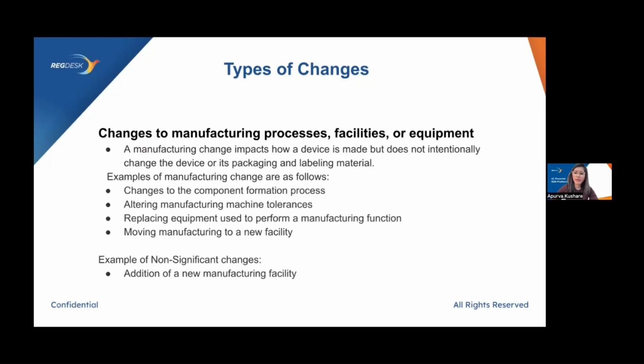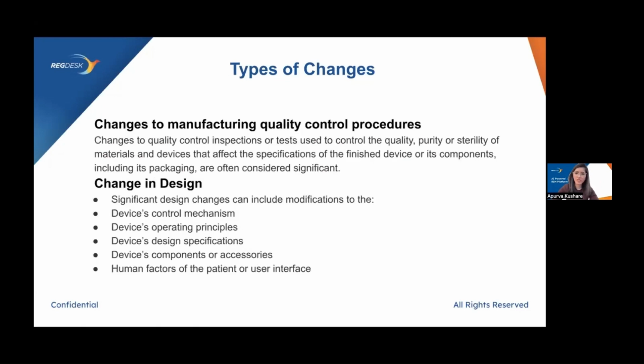So the next type of change we have is change to the manufacturing quality control procedures. An example of a significant change would be a change to the quality control inspections or tests used to control the quality, purity, or sterility of materials and devices that affect the specification of the finished device. So this is very important to consider. Changes to the finished device or its components, including its packaging, are often considered to be significant changes.